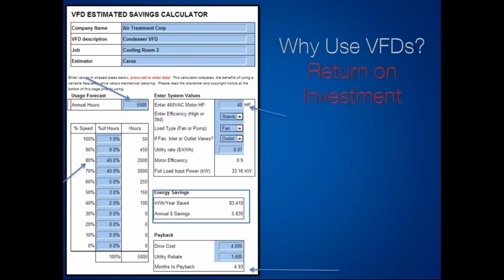Furthermore, you do have access to a VFD savings calculator, okay? This is an example that we have on our website, and basically what you'll do is you go in and you plug in all of your job site data. So you're plugging in your motor horsepower, when you're going to be running it, your voltage, what the application is, all the pertinent information. And from there, it's going to spit out the kilowatt-hours per year saved, the annual savings you can expect to see, and when you can expect to be paid back. I don't know if you guys can see that arrow at the very bottom of the page, but that says months to payback, almost 5 months. So that drive is going to pay for itself in 5 months. All right, next slide.